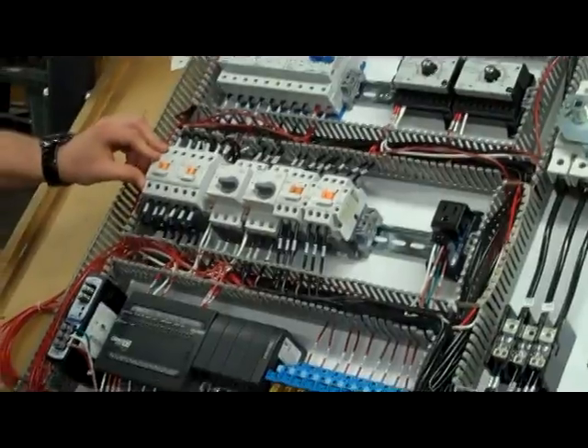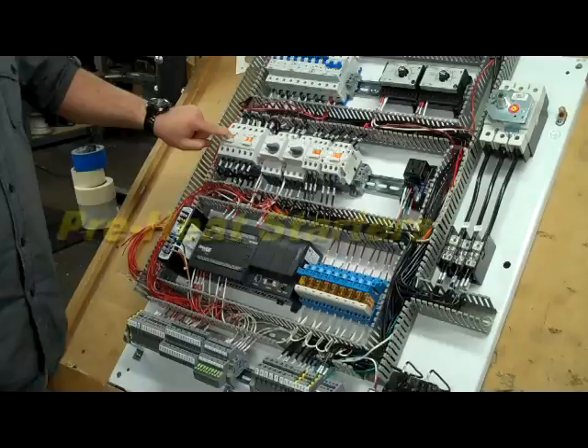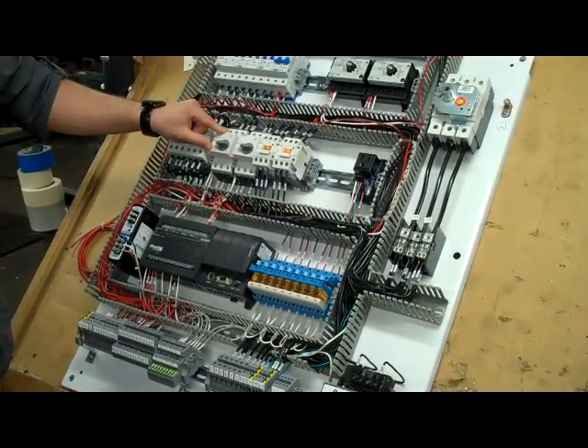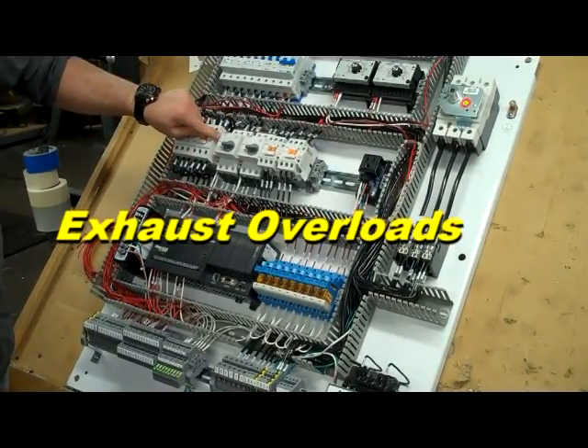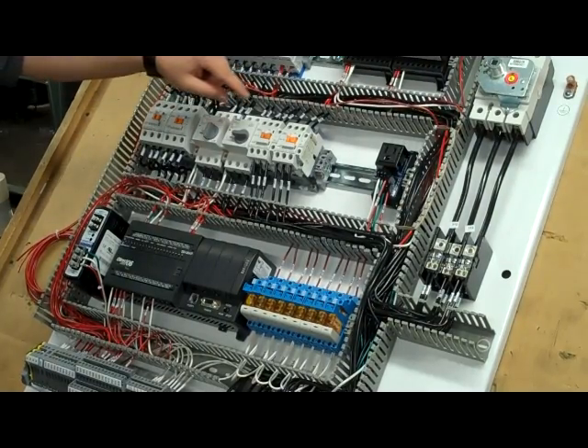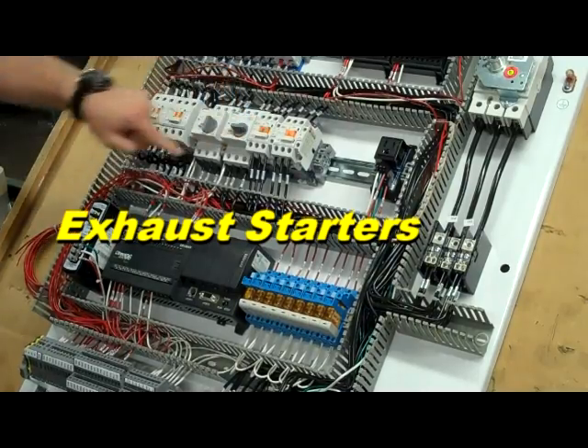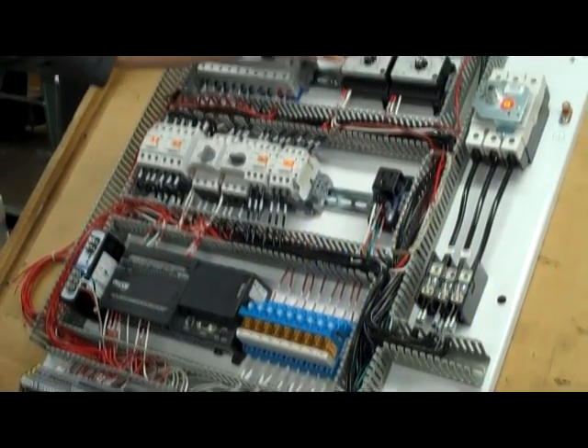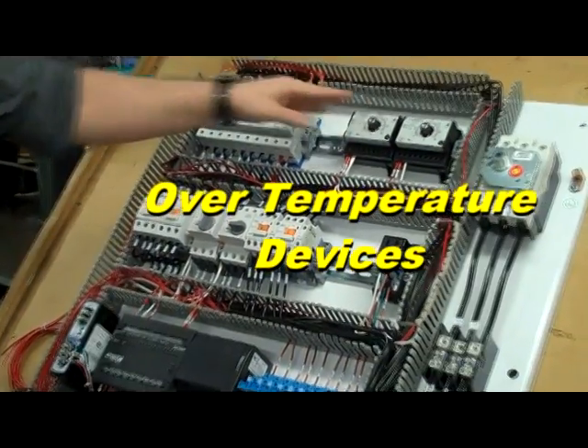The heater contactors energize the start-up preheat coils to each heater. These are the exhaust overloads, which trip if the amperage of the exhaust exceeds the preset amperage settings. The exhaust fans are started when these coils are energized. A 120-volt service outlet is provided here for convenience to power a laptop computer, for example. These exhaust over-temperature devices are used for protecting the fan and other equipment.